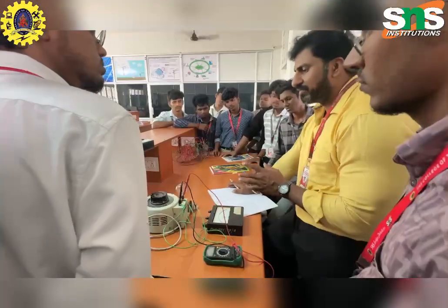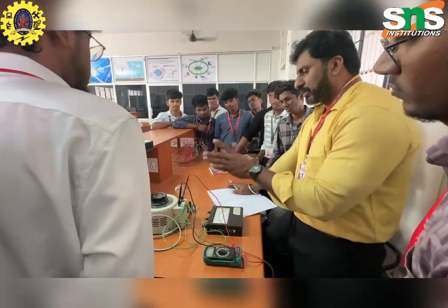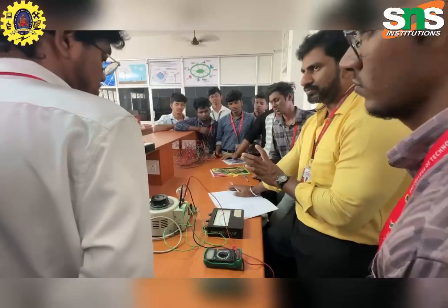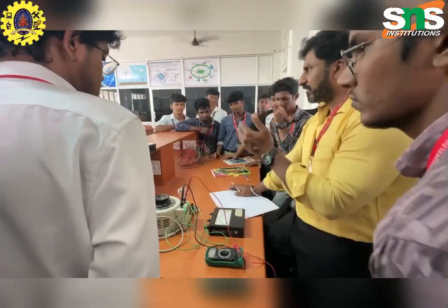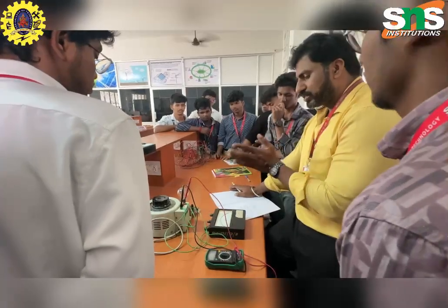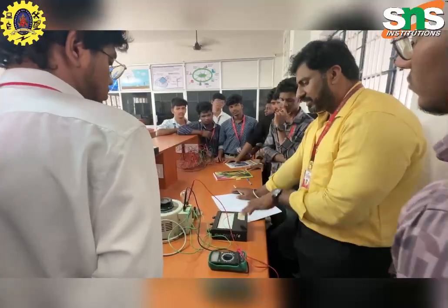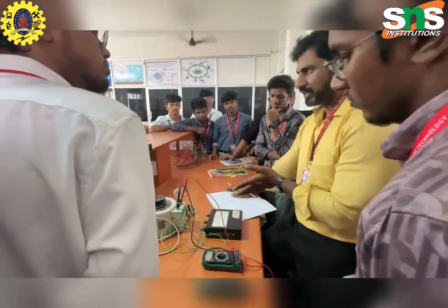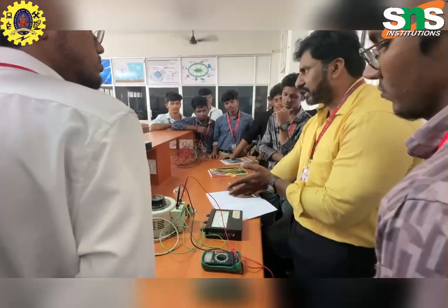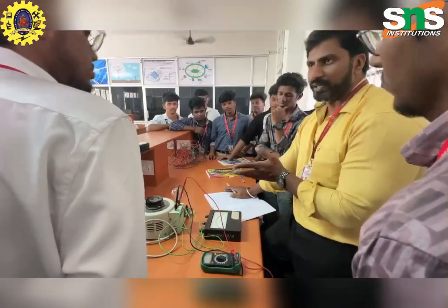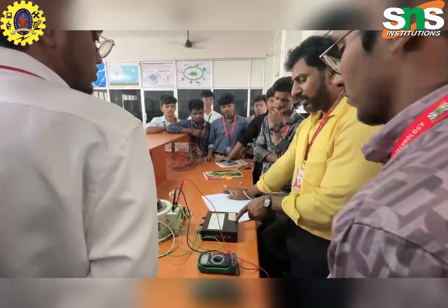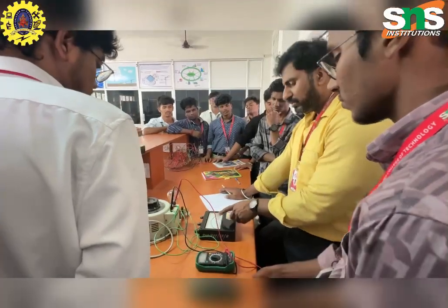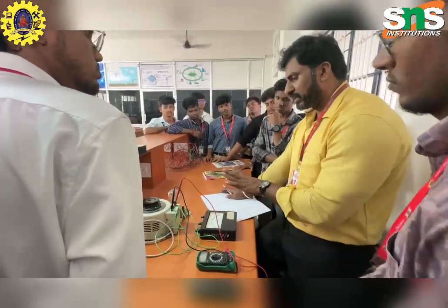A variac is nothing but a variable autotransformer. The supply voltage is 230 volts, and that is varied from 0 volt to 270 volt. From 0 to 270 we take 5 to 10 readings, and for each reading we see how much error there is. Based on that, we say whether this meter has error or is errorless. When the meter is errorless, there is no need to calibrate it. When the meter has error, we need to find whether it is a positive or a negative error. For positive error we need to tune the knob, which is connected to the spring of this meter. Calibration is the next process; first we need to find the error of the meter.